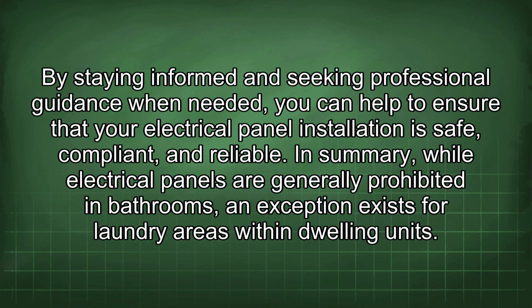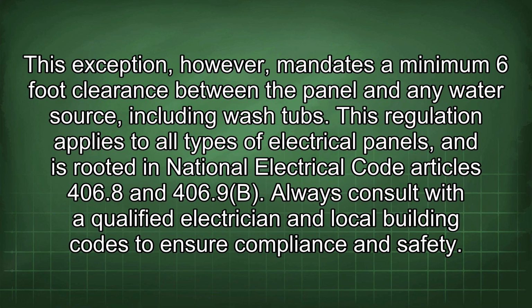By staying informed and seeking professional guidance when needed, you can help to ensure that your electrical panel installation is safe, compliant, and reliable. In summary, while electrical panels are generally prohibited in bathrooms, an exception exists for laundry areas within dwelling units. This exception, however, mandates a minimum 6-foot clearance between the panel and any water source, including wash tubs. This regulation applies to all types of electrical panels and is rooted in National Electrical Code Articles 406.8 and 406.9b. Always consult with a qualified electrician and local building codes to ensure compliance and safety.